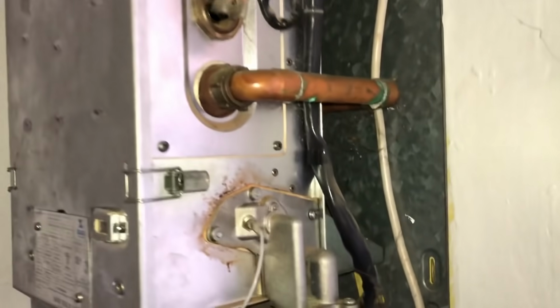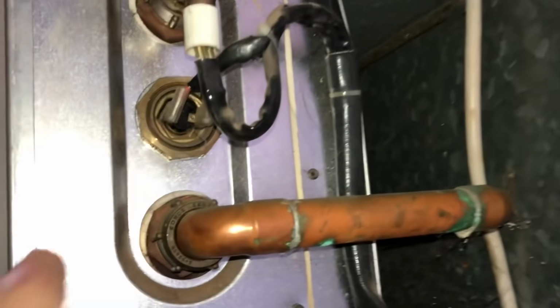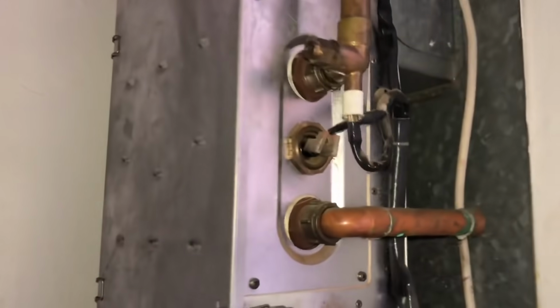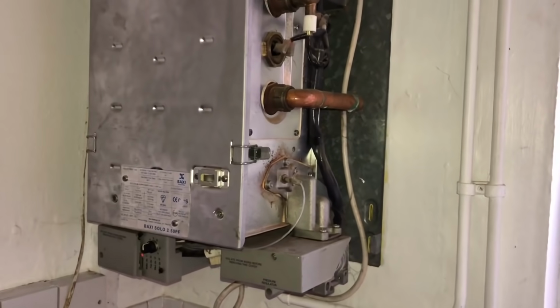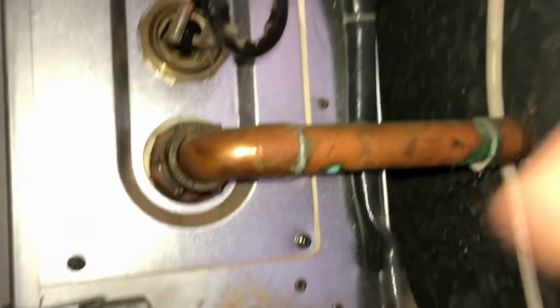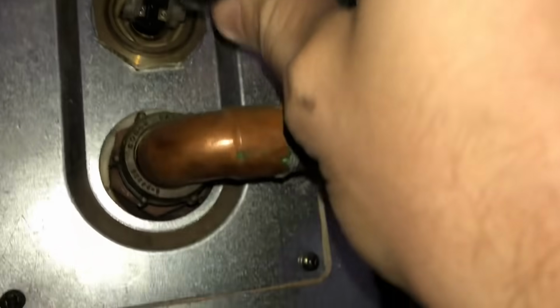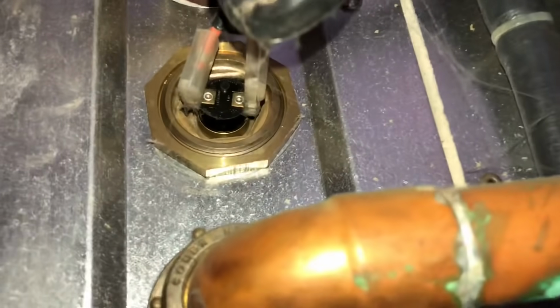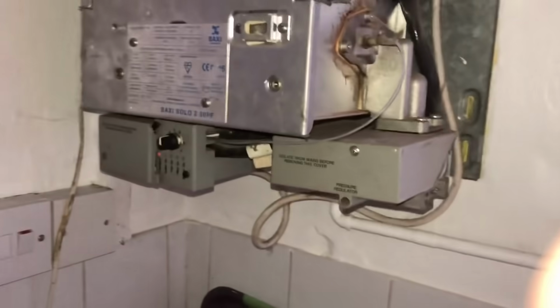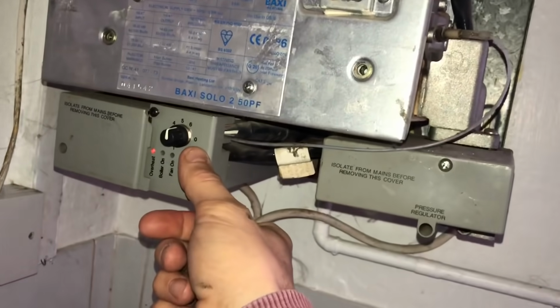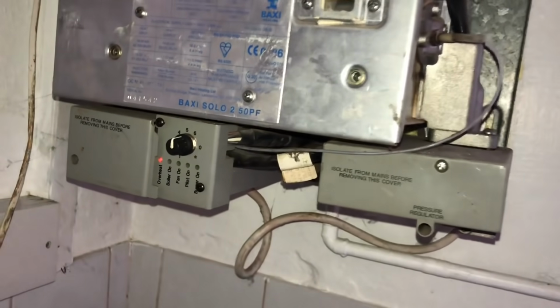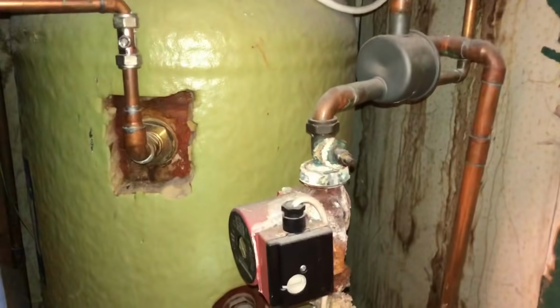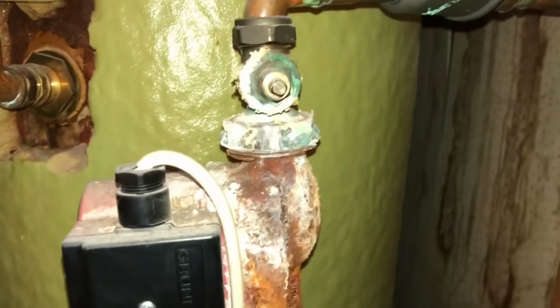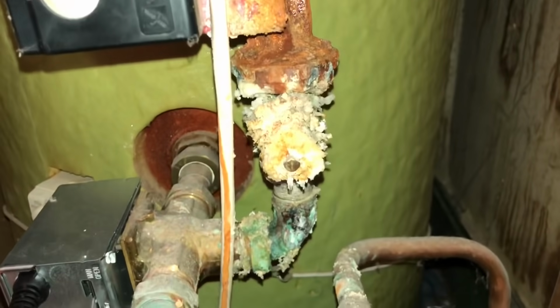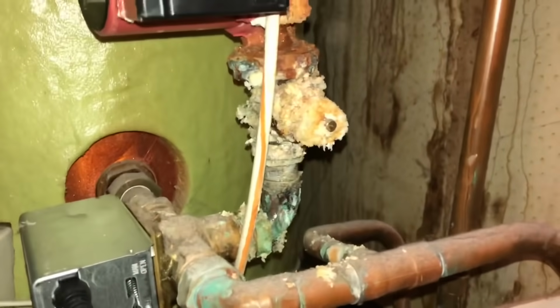Now some boilers you'll have to take the cover off, locate the overheat stat, and there'll be a little red button on that you will physically have to reset yourself. This one's not got the button. You can see there's no button on it, so the case of resetting this will be on the actual board itself. If there's not a reset button on there, normally you can reset a boiler by turning it to 0 and back up again. So with any overheat problem, the first thing I'll look at is the pump, because overheating of a boiler can be caused by no circulation or poor circulation.